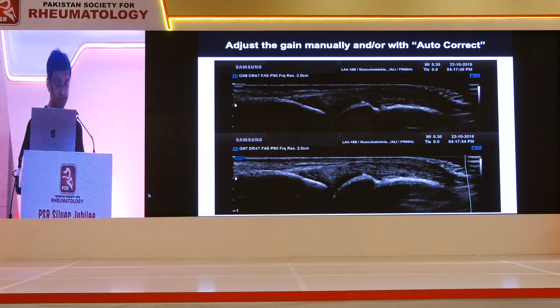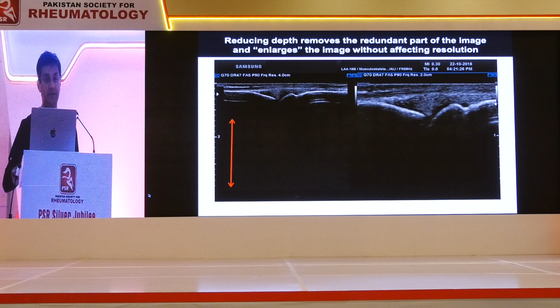The next thing is the depth. So you can see that in these 2 images, the only thing that's changed is the depth. If you have an image like this, all of this area is completely wasted information. The machine is trying desperately for the sound waves to get through the bone and try and give you information from down here. But actually, it can't give you information from down here because the sound waves aren't getting through the bone. So you're actually just wasting the computing power and your probe ability by having your image like this. Actually, if you just adjust your depth, you can get a much better resolution because the machine is then concentrating the near zone resolution and giving you a much better image.